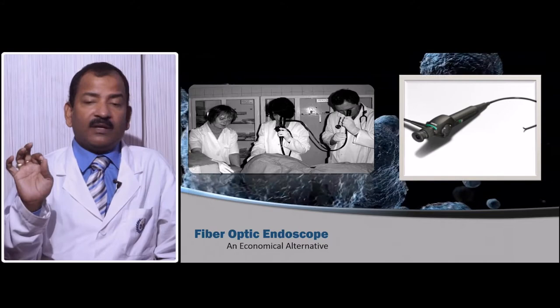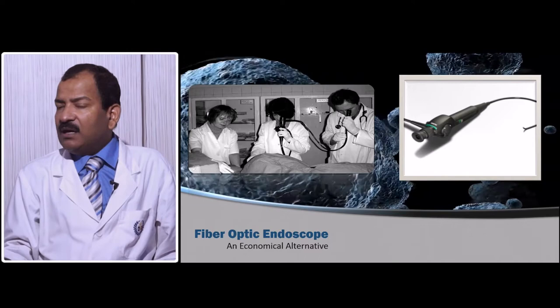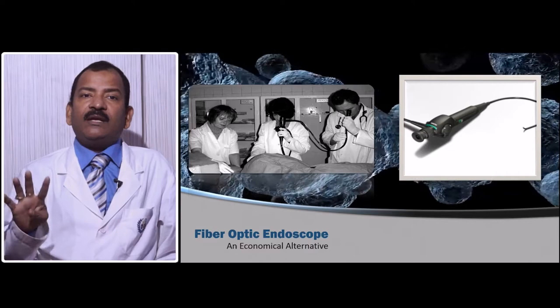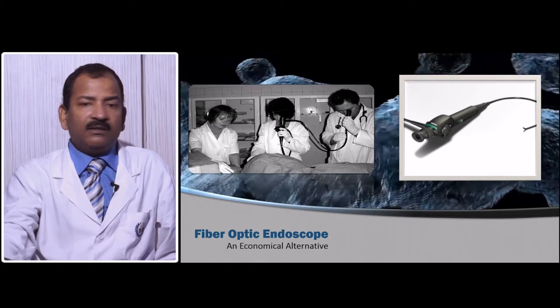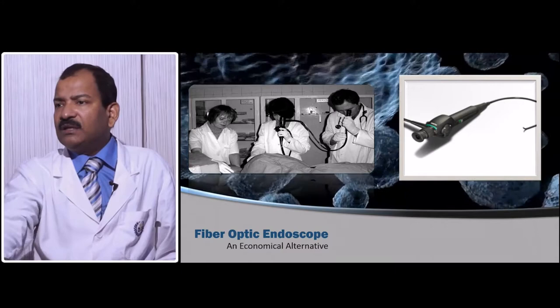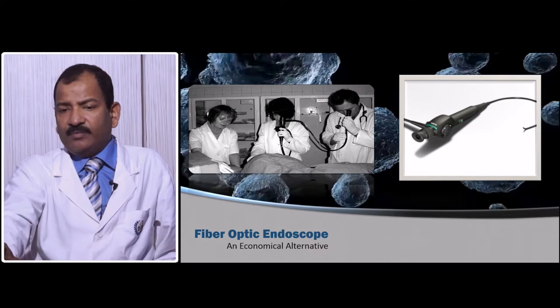The advantages of fiber optic endoscopy: it is very handy — if you are a freelancer, you can carry it in a briefcase and travel from place to place. It is also cheap; you can buy an upper GI endoscope for around 1 lakh rupees, making it a good alternative for rural areas where patients cannot pay more. Maintenance is also not risky — it is easy to maintain because there are no electronic parts and no risk of voltage fluctuation.